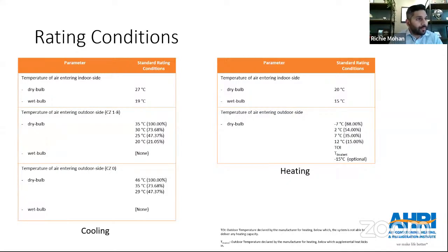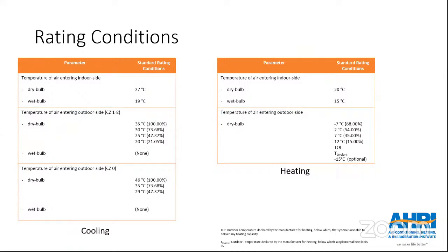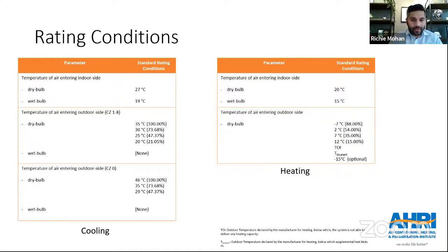And the other thing - the same would apply to the issue about the indoor dry bulb, which is 27 degrees Celsius. If there's a way we can look at another indoor dry bulb temperature, from 27 to maybe even 23, we need to assess the impact on the efficiencies and the impact on the work. If there's a way we can make that happen right now, in the first iteration itself, then we should definitely do that. We need to run this by the committee again within the global standard and see whether there's a possibility and feasibility of reducing 27 to perhaps even 23 or 22.